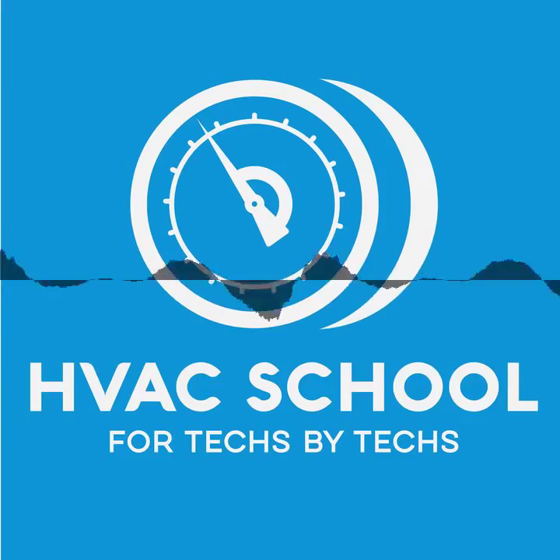The other thing that I recommend is do not do an overnight pressure test, because nitrogen, just like any other refrigerant gas that we use, will change the pressure based on temperature. So if it was nearly 90 degrees yesterday and I pumped my system up to 600 pounds, I come back this morning and it's in the low 60s. I may well think I have a leak when I really don't. So make sure that your pressure test is done during basically the same outdoor ambient temperatures. Otherwise, again, you can think you have a leak when you really don't.